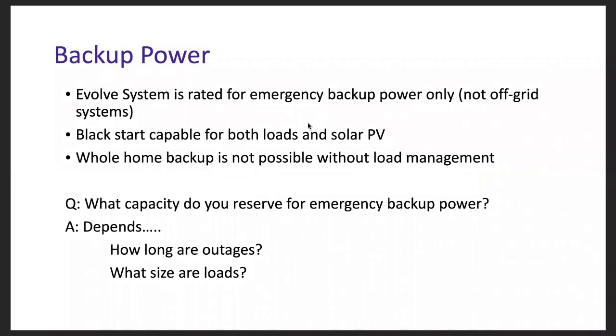The Evolve system is rated for emergency backup power only. It's not intended for off-grid use only. Black start capable for both loads and solar PV. That means that it goes from being a current source synced to the grid voltage while grid tied to being a voltage source when the grid goes out. And that voltage source will, of course, serve the backup loads as well as provide a synchronizing voltage to the solar PV to produce an off-grid mode.